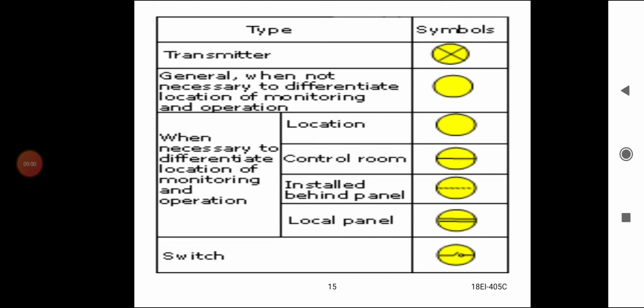In general, when it is not necessary to differentiate the location of monitoring and operation, just show the circle. When necessary to differentiate the location of monitoring and operation, a general instrument at a control station has a line inside the balloon or circle. Installed behind the panel, it shows a dashed line inside the balloon. Local panel shows double lines inside. Switch: inside the balloon or circle, there is a switch symbol.